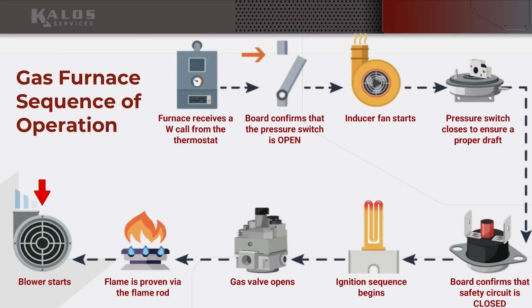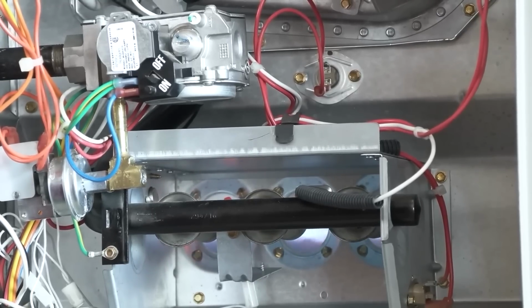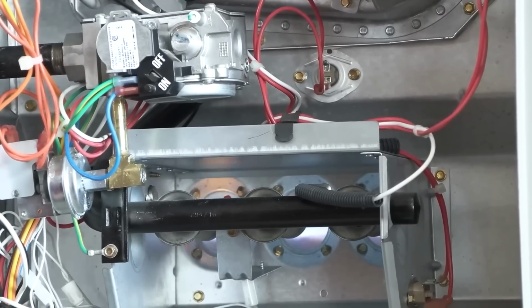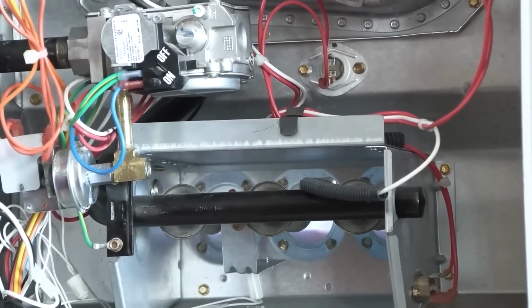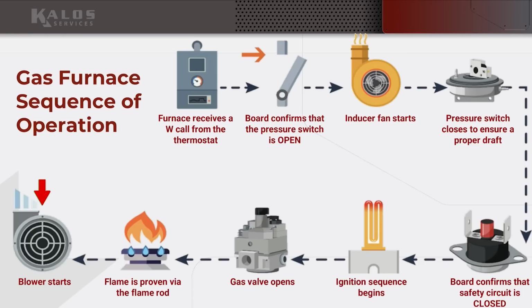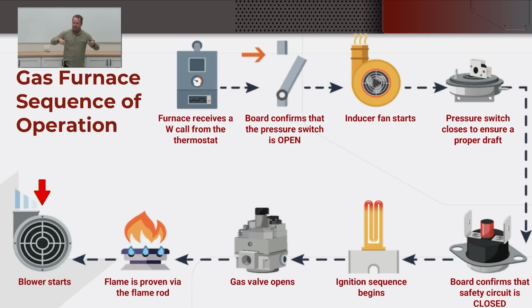Final thing is blower starts. When that blower starts, with the panels on the blower section, watch that flame. Get in the habit of doing that on every maintenance, every system you install. Because if you watch a flame and the blower starts and the flame starts doing this to you, orange flame, all that kind of stuff. Now, a tiny bit you may get just because there are tiny little gaps and cracks in the cabinet, especially when you had the panels off, whatever. So a little tiny bit, but it should stabilize very quickly.